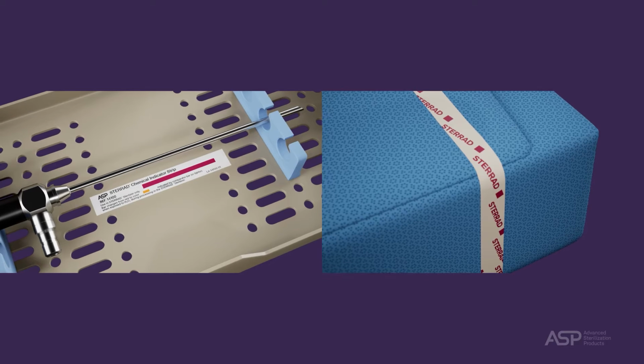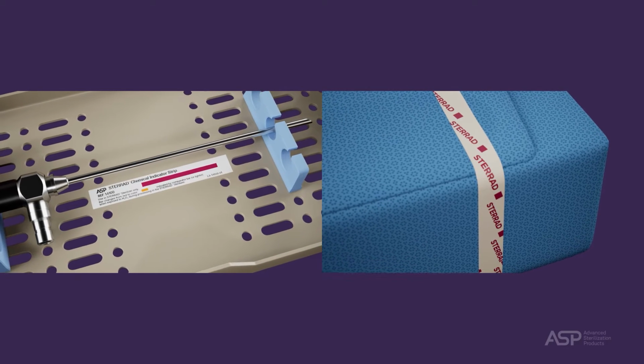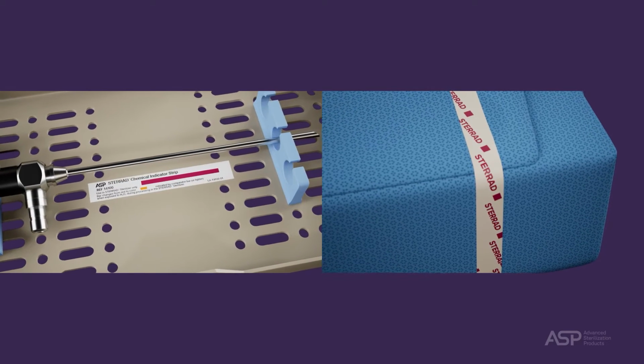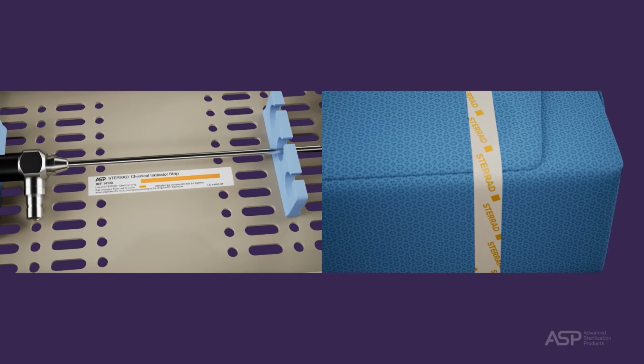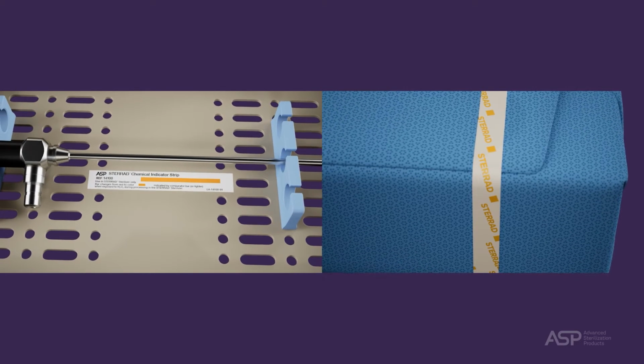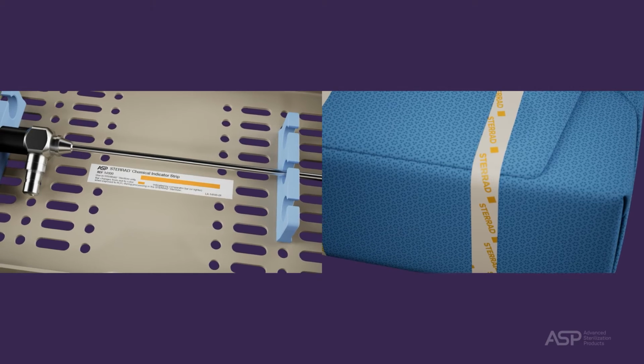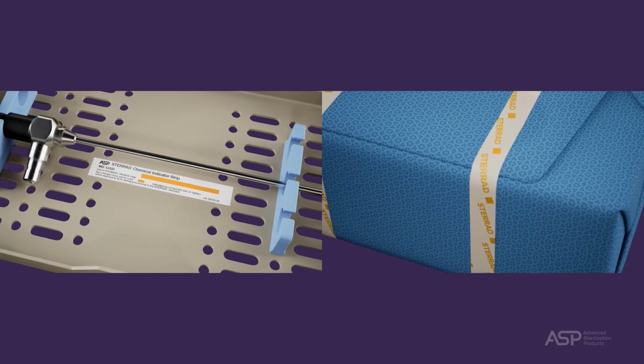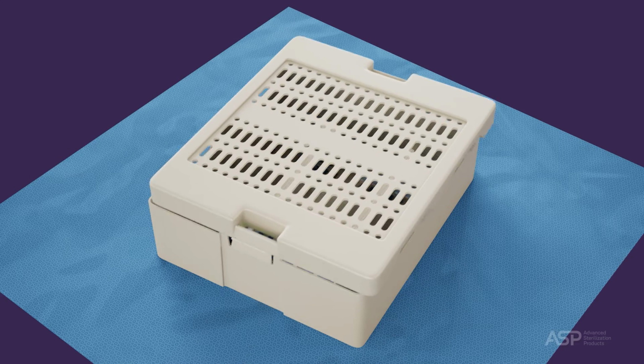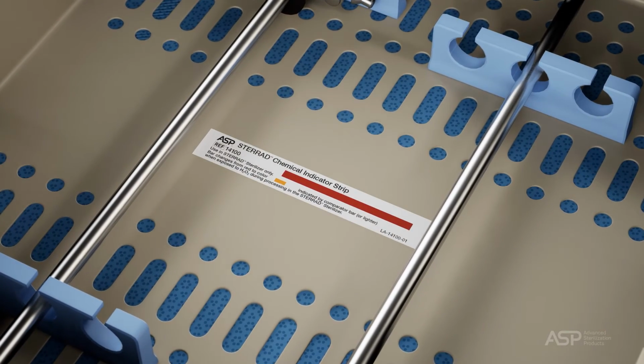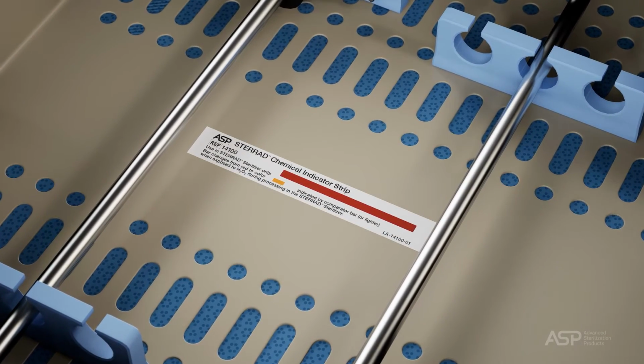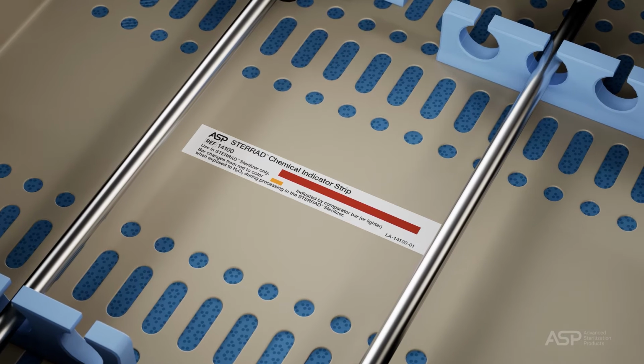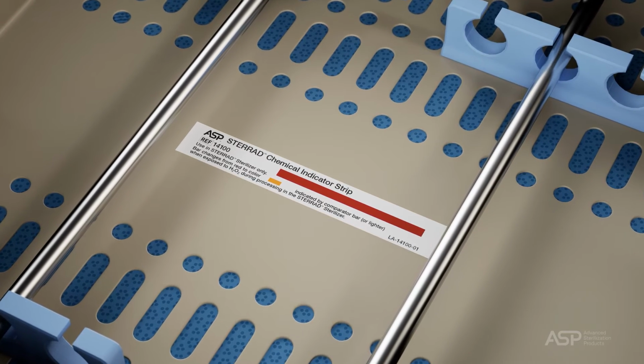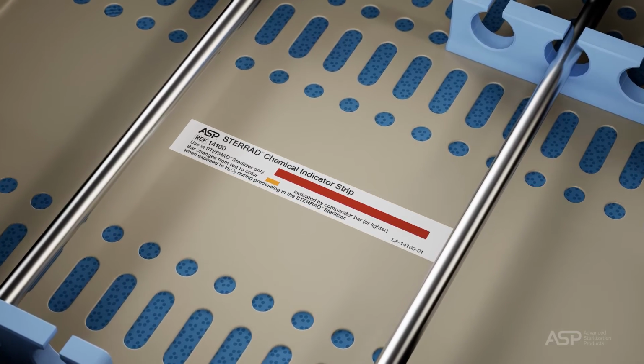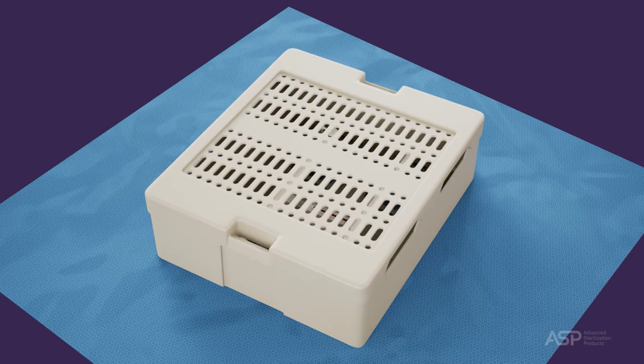The STERRAD chemical indicator (CI) strips and SealSure chemical indicator (CI) tape change from red to yellow or lighter, indicated by the comparator bar, when exposed to hydrogen peroxide during the processing in the STERRAD sterilizer cycle. If the indicator bar has not completely changed from red to yellow or lighter, as indicated by the comparator bar, introduction of hydrogen peroxide, an essential component of the STERRAD sterilization cycle, may not have taken place.